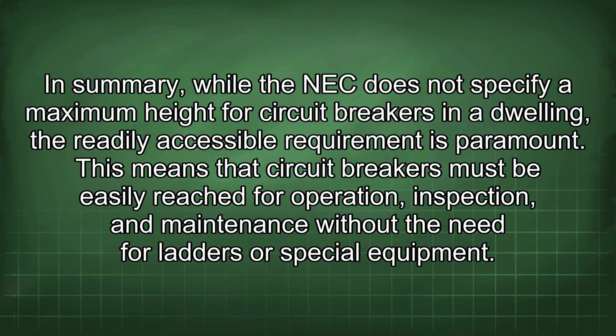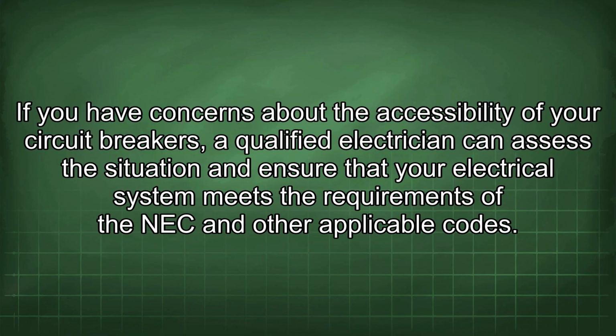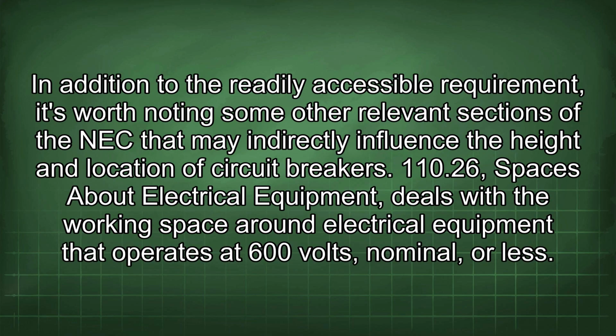This means that circuit breakers must be easily reached for operation, inspection, and maintenance without the need for ladders or special equipment. If you have concerns about the accessibility of your circuit breakers, a qualified electrician can assess the situation and ensure that your electrical system meets the requirements of the NEC and other applicable codes. In addition to the readily accessible requirement, it's worth noting some other relevant sections of the NEC that may indirectly influence the height and location of circuit breakers.